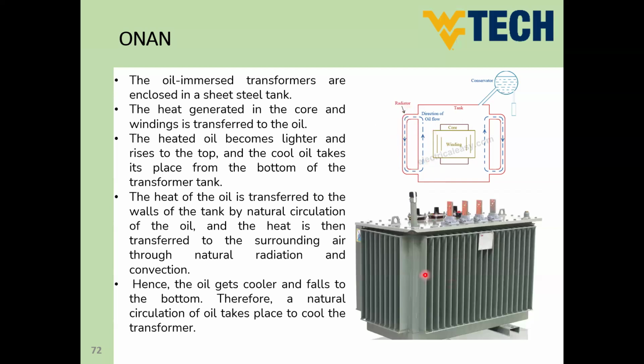So you have a lot of slices here. These slices represent the radiator in order to dissipate this heat outside of the transformer. So this is natural. We don't have any kind of forced air or fans here. The oil will be cooled by dissipating this heat through the slices of this heat sink, and will return back again to the bottom of the transformer to continue cooling our transformer. Okay, so this is the shape of the oil natural air natural circulation of a transformer.